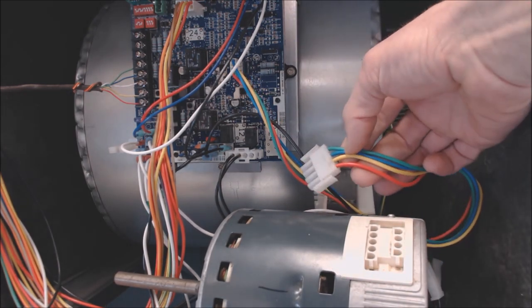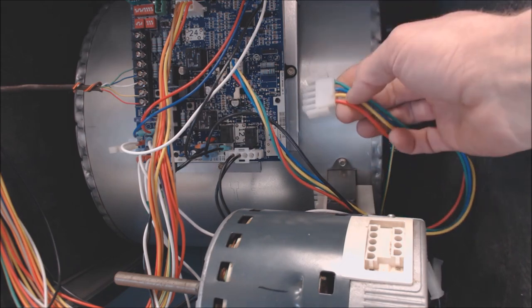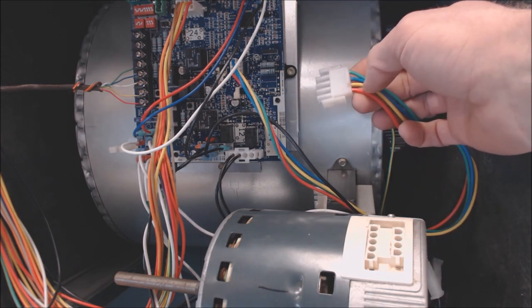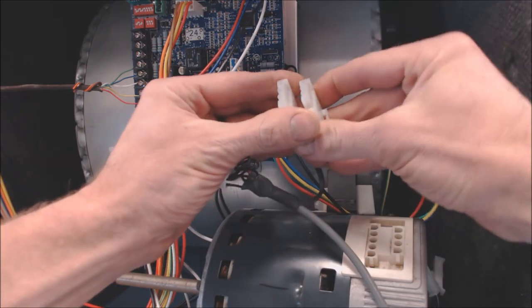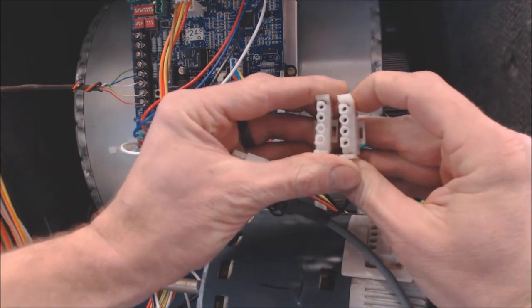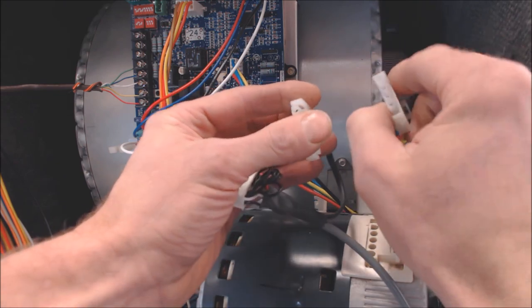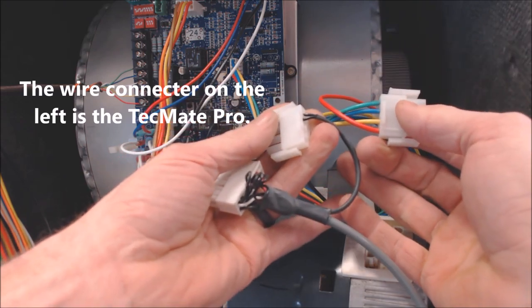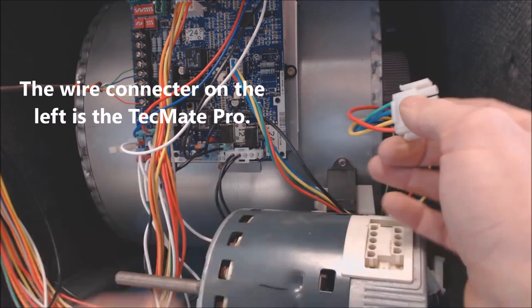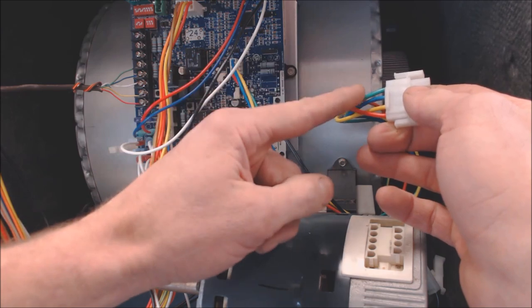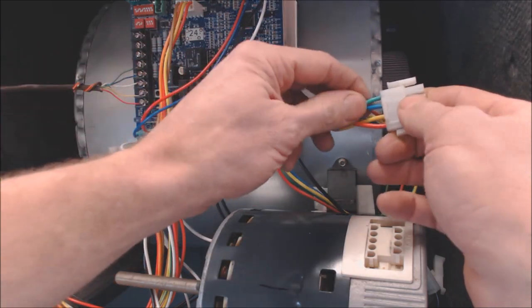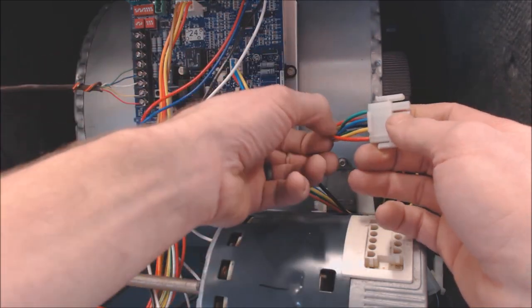So right here, this is the connection. And if you compare this connection to this connection, those look just the same. And you notice that only two wires are actually powering with 24 volts. So even though this control board here sends DC millivolts to the blower motor to tell it what speed to turn on...